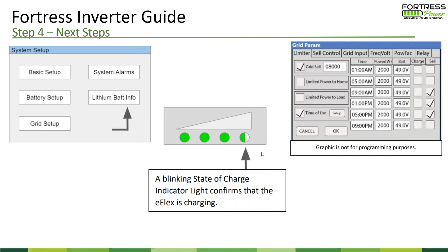I want to talk about layout real quick. I know we're at the end of our hour, so we'll probably have to do email follow-up for remaining questions. One common design configuration we see is putting the eVault directly in front of the Sol-Ark. National Electric Code requires the accessibility depth to be no greater than 6 inches between the front of the eVault and the front of the Sol-Ark, so the simple solution is to place the eVault off to the left of the Sol-Ark.